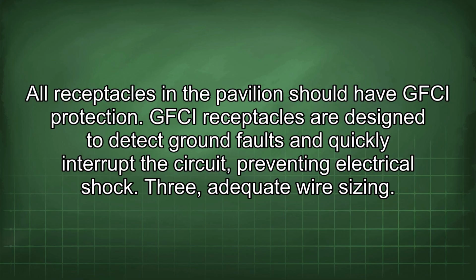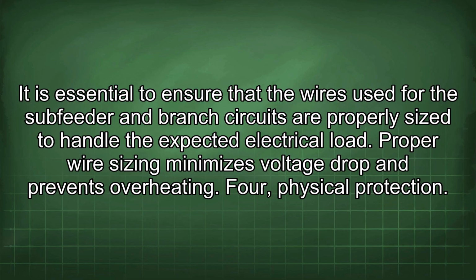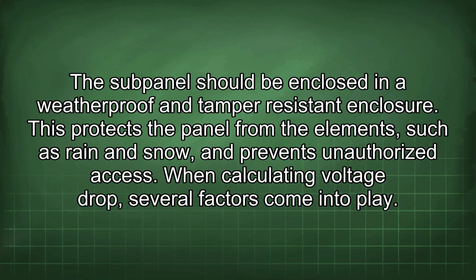3. Adequate wire sizing. It is essential to ensure that the wires used for the subfeeder and branch circuits are properly sized to handle the expected electrical load. Proper wire sizing minimizes voltage drop and prevents overheating. 4. Physical protection. The subpanel should be enclosed in a weatherproof and tamper-resistant enclosure. This protects the panel from the elements, such as rain and snow, and prevents unauthorized access.